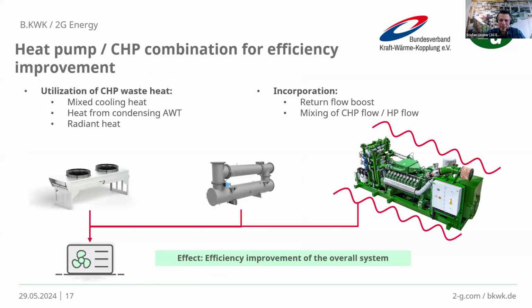Also, this is a more technical slide. This combination brings a lot of benefits because also from a thermodynamical perspective, you can combine it. Of course, with the CHP you have a lot of waste heat you cannot use. But what you can do is use the waste heat to increase the efficiency of a heat pump, an air-water heat pump, for example. So there are lots of thermodynamical opportunities that make this combination highly viable.